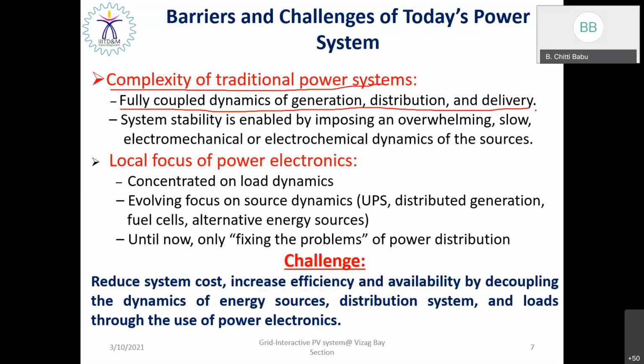Second, as we promote renewable power generation, the renewable energy sources are basically a fragile power generation system. They do not have any inertia. Inertia is a very important component in an electrical power system, in order to damp out any oscillations that occur in the power system or in the transmission line, internally or externally. As renewable sources don't have any inertia, they are basically inertialess systems. System stability is enabled by imposing the overwhelming, slow electrochemical dynamics of the sources. Let's talk about fuel cells. If you use fuel cells in a power system, the dynamic response of the fuel cell is very sluggish. This is another important difficulty we face in today's power system.